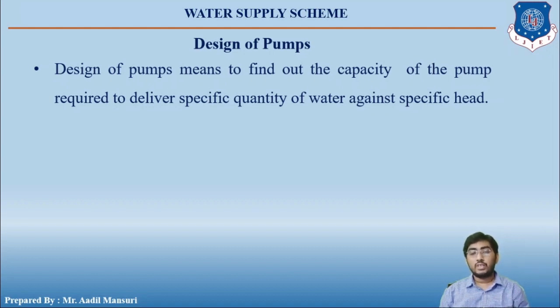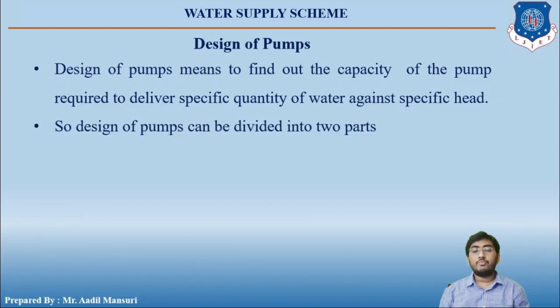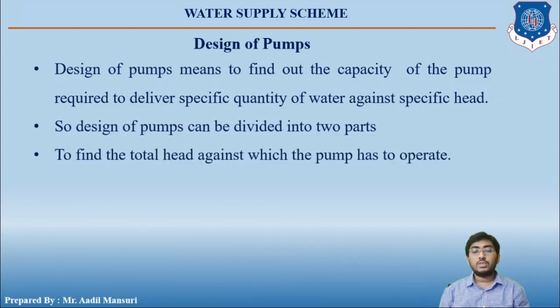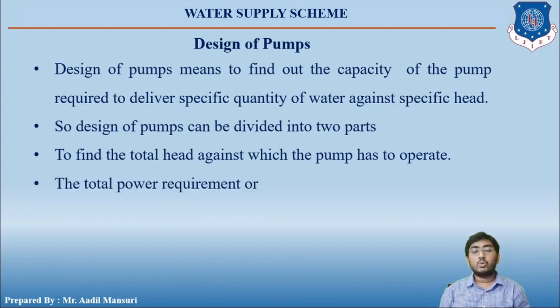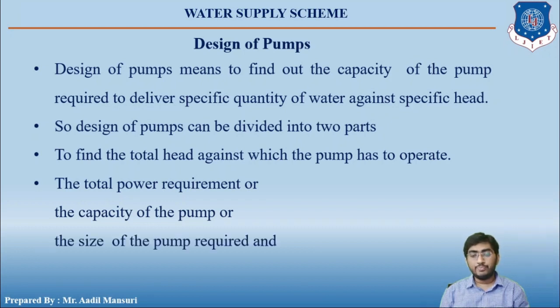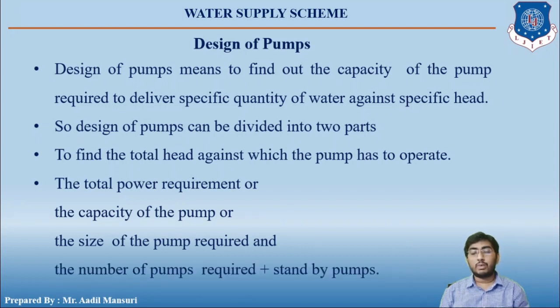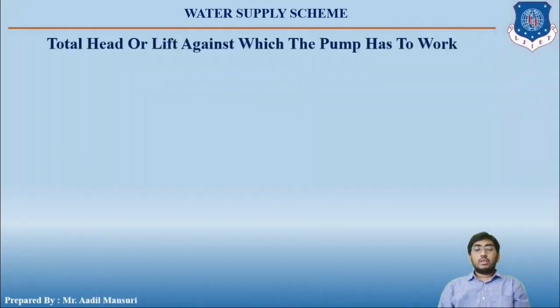Design of pumps can be divided into two parts. The first is to find out the total head against which the pump has to operate — that is the total height to which the water is to be pumped. The second is the total power requirement, or the capacity and size of the pumps required, and the number of pumps required plus standby pumps.